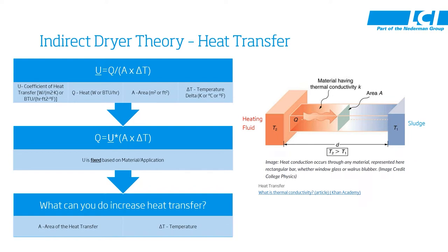Now we know U is fixed based on the material and application. So what can we do to increase the heat transfer? We either have to increase the area of heat transfer — which means a bigger dryer, a larger building, cost, etc. — or we have to increase the delta T, which means we have to increase the temperature of the heating fluid. There's only so much temperature we can use on the heating fluid, so it's a limitation as well.